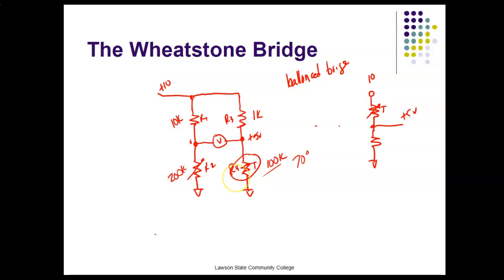You connect this circuit over here. So I would come over here, and my thermistor has leads coming off. I would take it and put it in a glass of ice water with ice floating around in it, right? And this would give us pretty close to 0 degrees centigrade. Or I could decide 0 would actually equal 32. It's up to you and your instrument, right? Then I would adjust this until my meter measured 0. Now, if the temperature goes up, I would set it up so that my voltage goes up, and when it goes down, it would go negative.